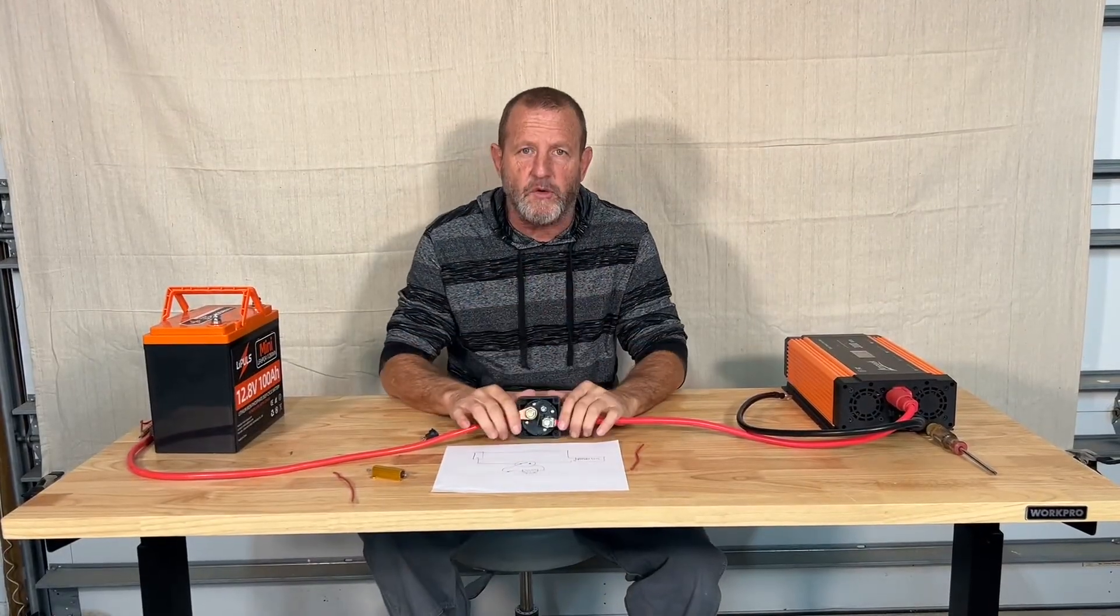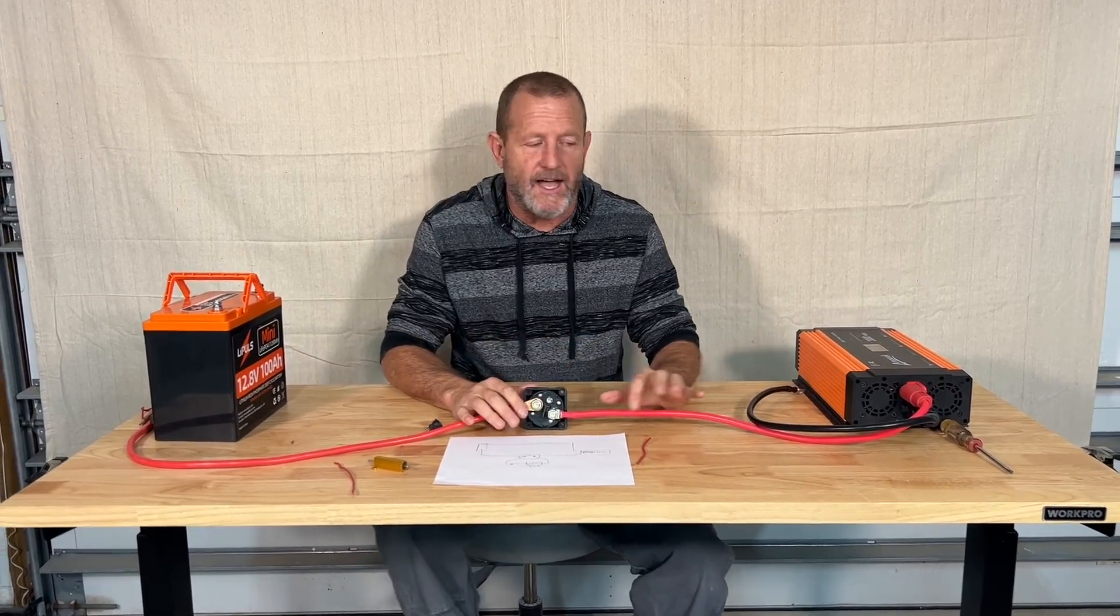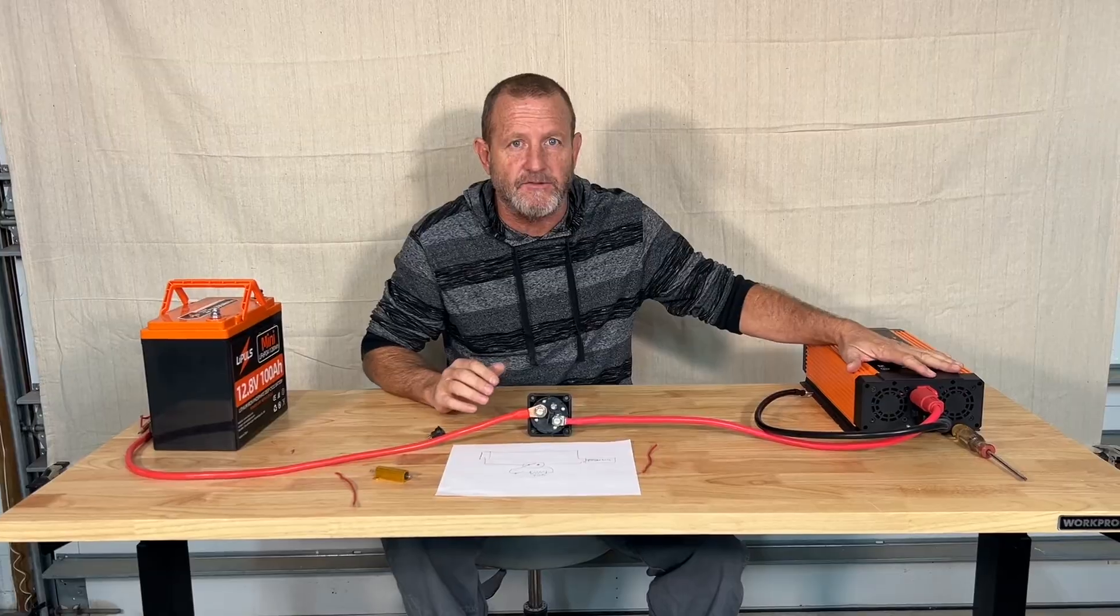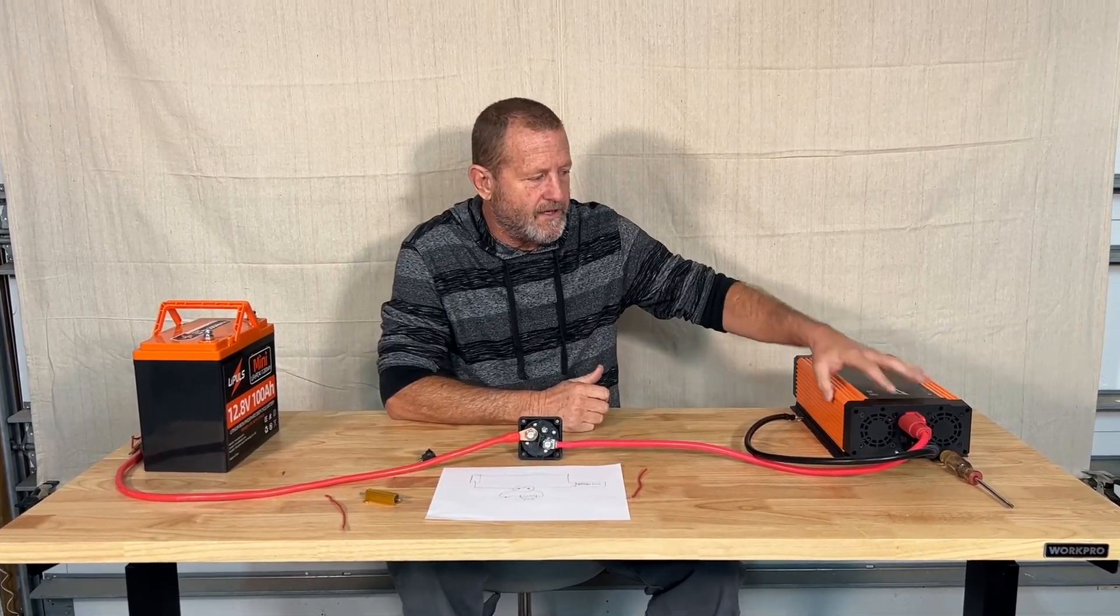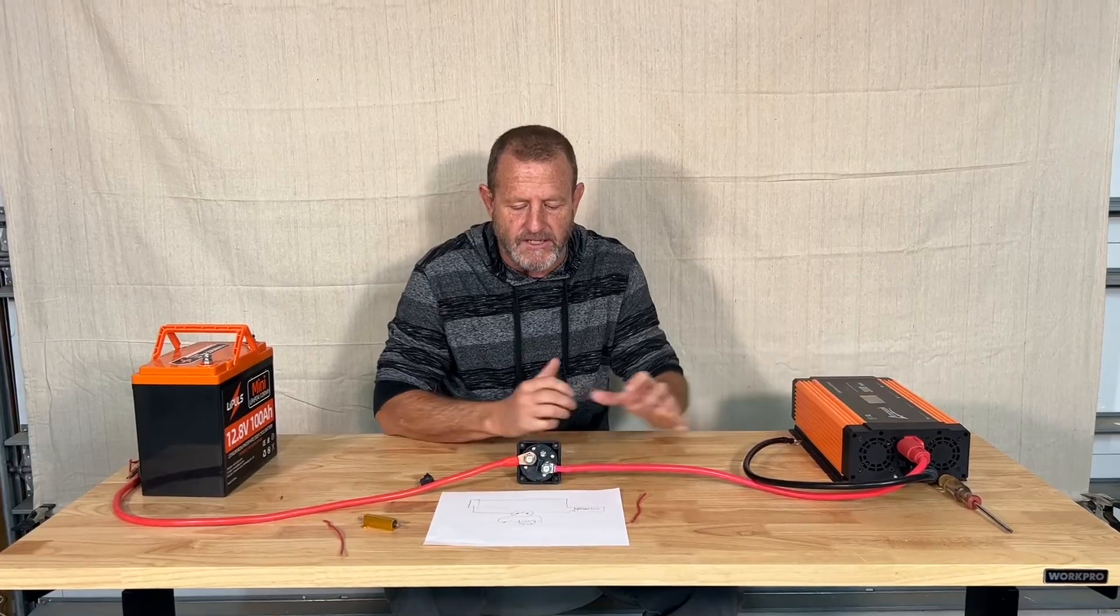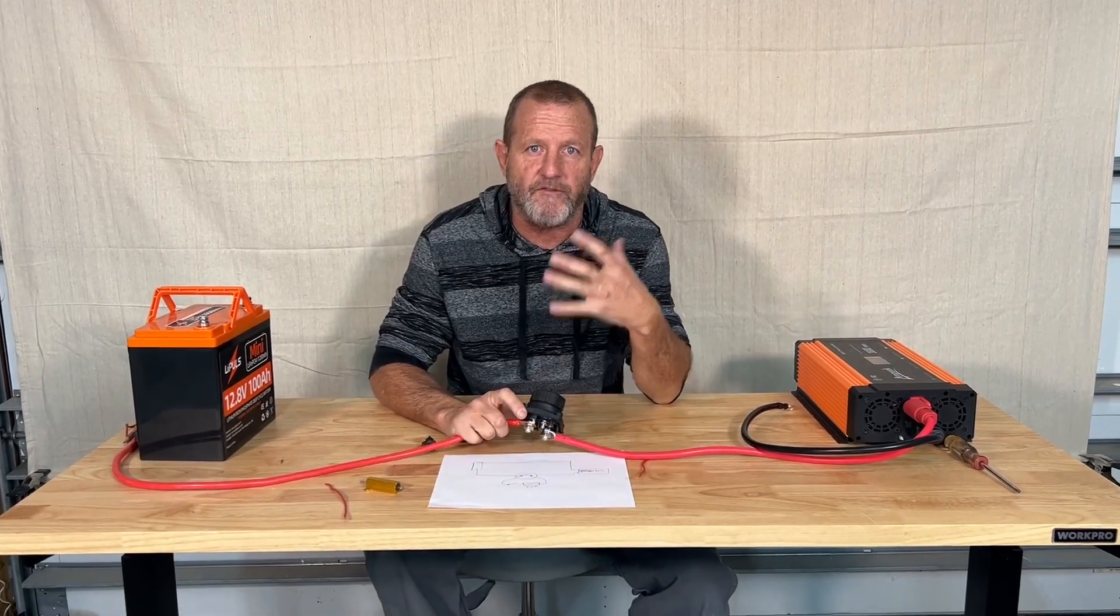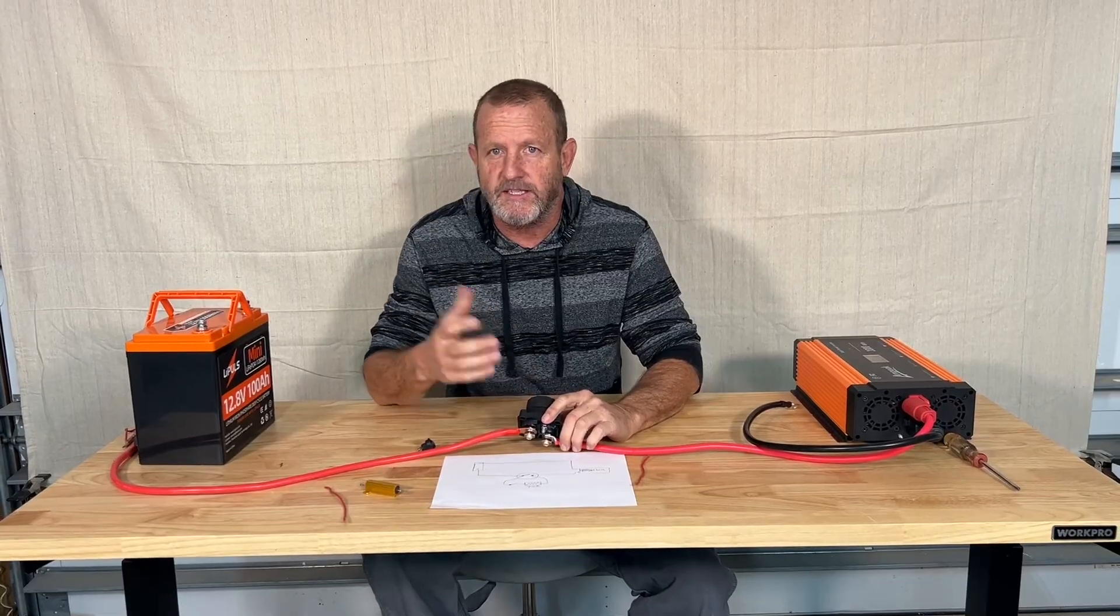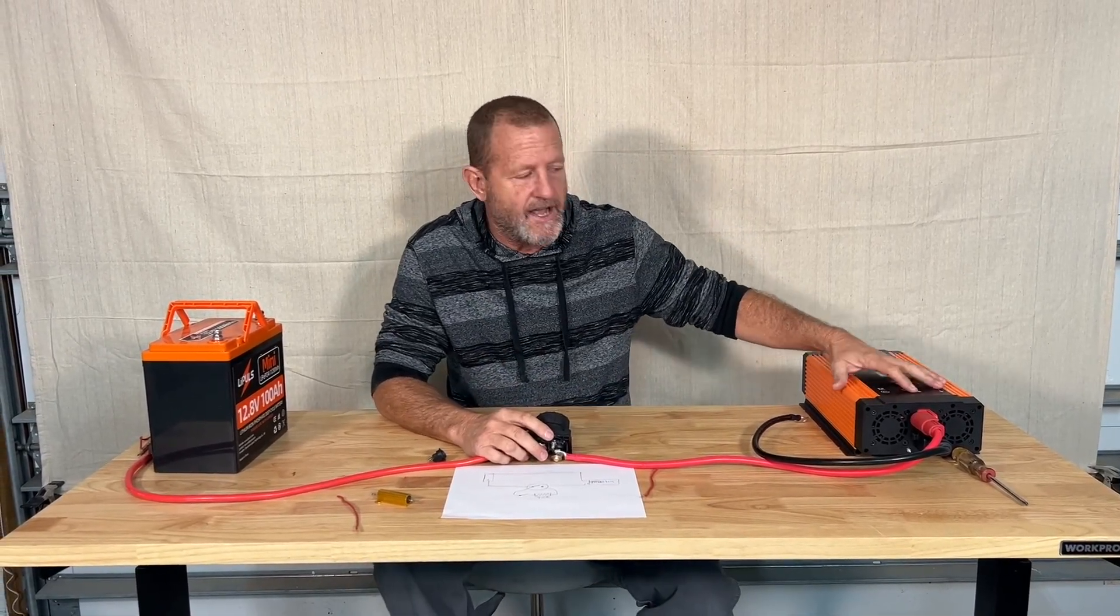Let's talk about a pre-charge circuit if you have a switch in place. We just went over if you just have your lines and you're hooking up your battery directly to your inverter, that initial hookup to prevent that inrush into the capacitors, but what if we have a switch, and we shut that switch off and our camper's sitting for a couple of days, these capacitors are going to drain down.